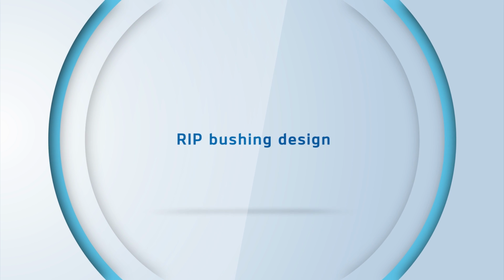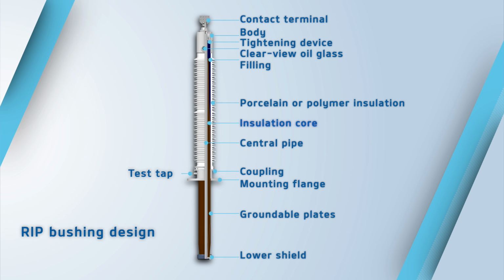RIP bushing design. An RIP insulated bushing consists of the following main elements: the solid insulation core made by insulating paper winding on a central tube with subsequent epoxy compound impregnation. RIP insulation is such. The paper winding layers are separated with conductive layers or insertions for leveling up electric field. Central flange mounted on the insulation core. Test tap kept in electric contact with grounded insulating layer. Mounting flange for the bushing installation in a transformer.